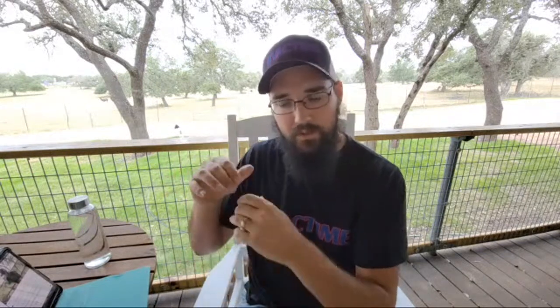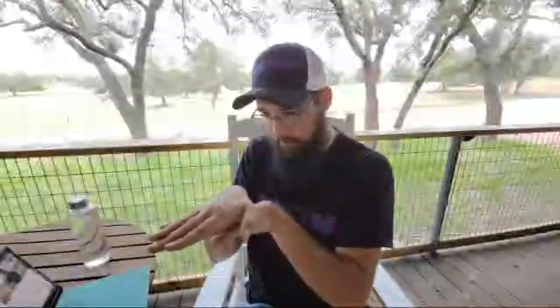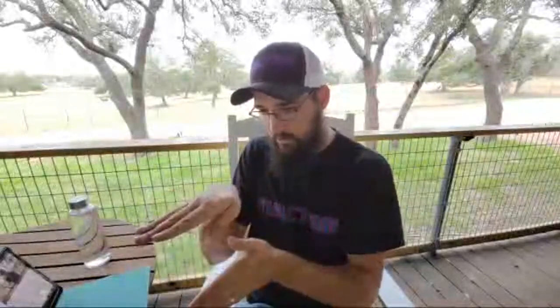I didn't film any of this, but I figured I'd talk about it. What I ended up finding was, when I opened the panel to the return section, filters, and backside of the evaporator coil, there was a white calcium water stain on the panel floor of the RTU between where the return drops down and the filter rack. I thought that was interesting and wondered what it was about. When I pulled one of the filters out on the bottom row, I noticed the bottom of the filter had gotten wet. Then I looked into the track of that filter tray and saw the same calcium deposits there.